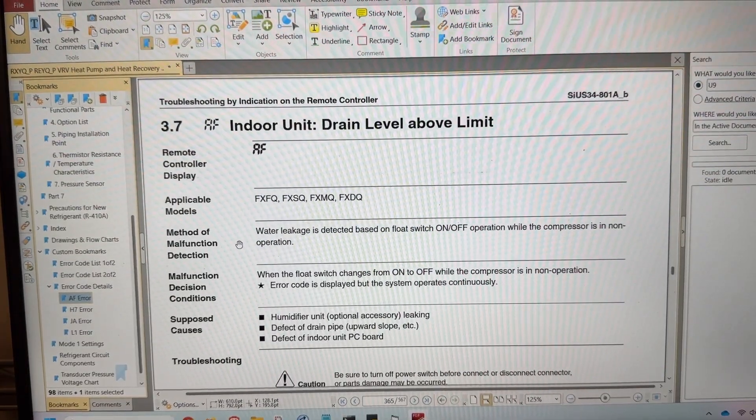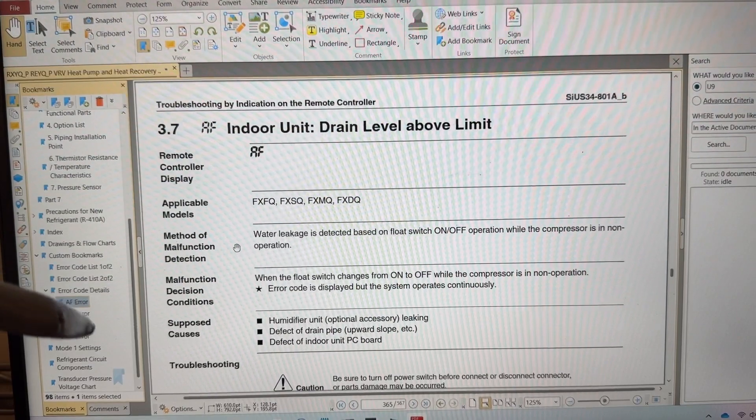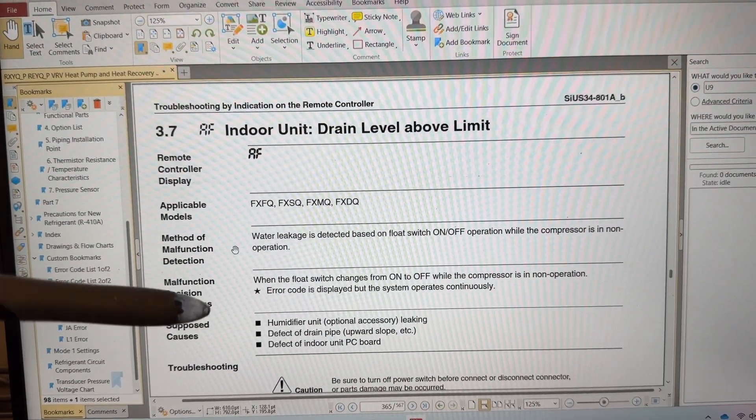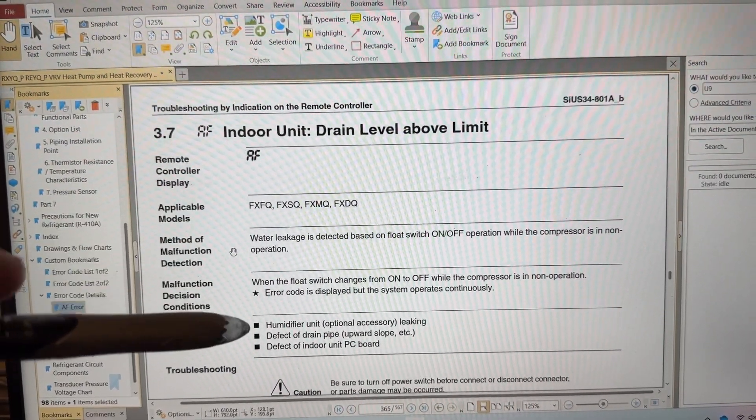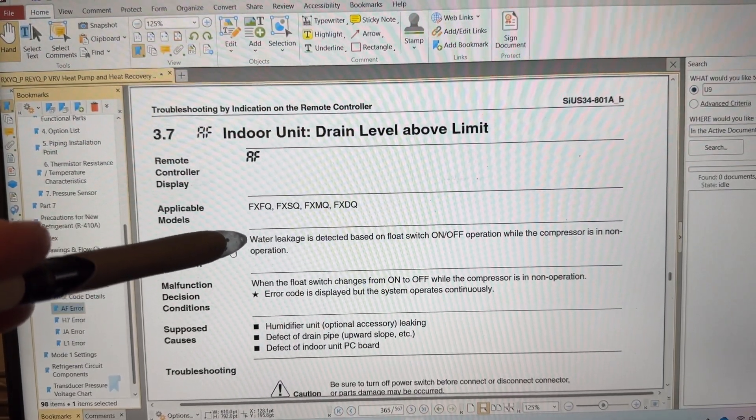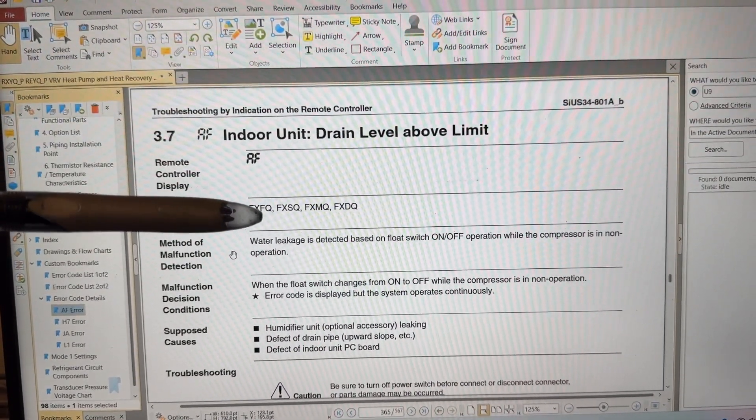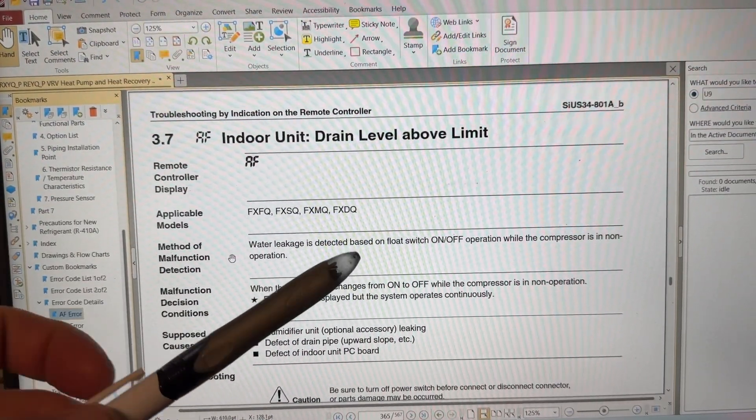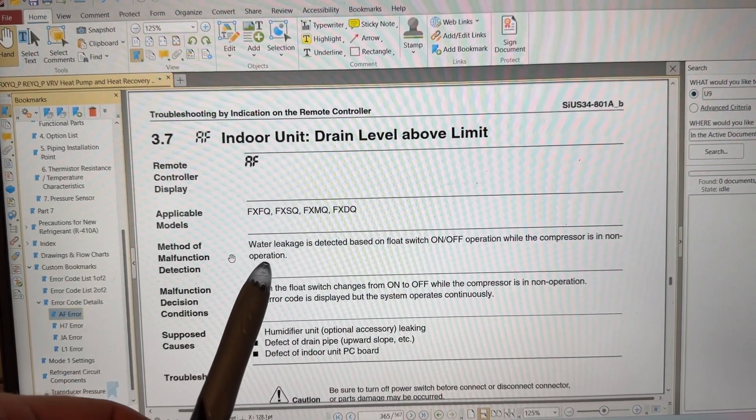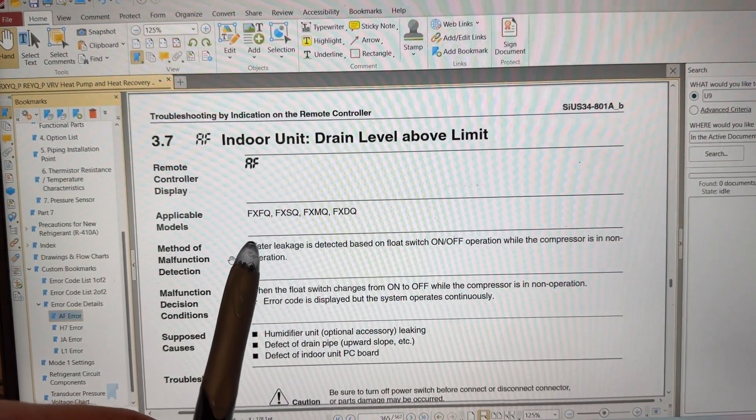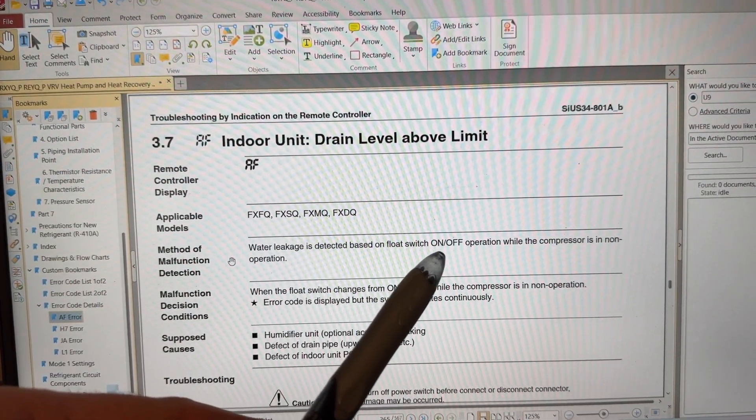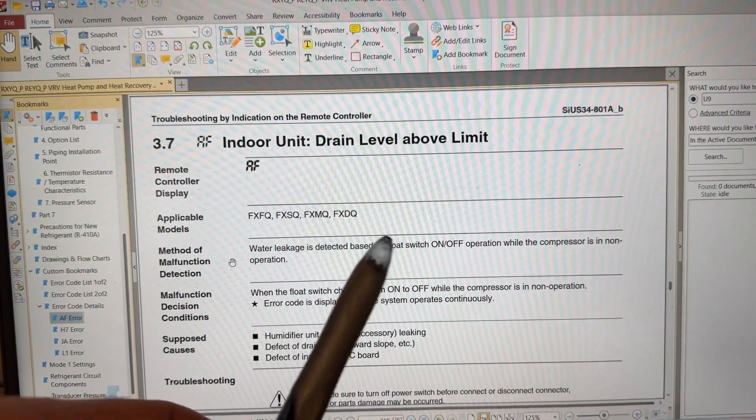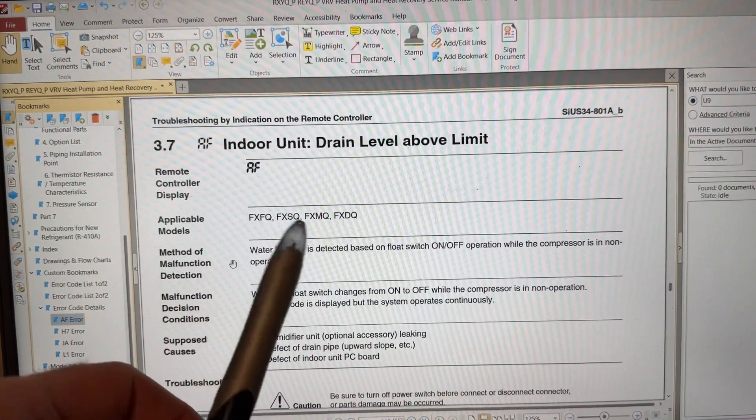I always like to look at codes before I start troubleshooting no matter how many times I've dealt with it, because one of the worst things that you can do is have tunnel vision as a technician and be narrow-minded when you're going into a problem. So I like to look at all the possibilities. Here's the definition. Water leakage is detected based on float switch on off operation while the compressor is non operation.